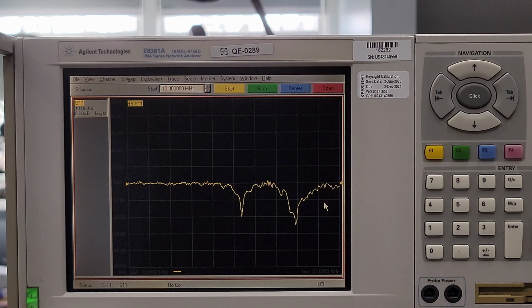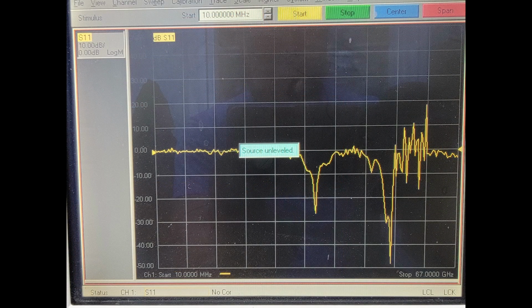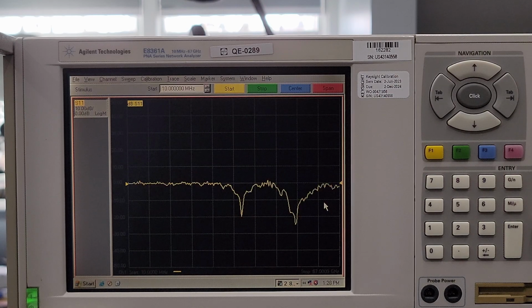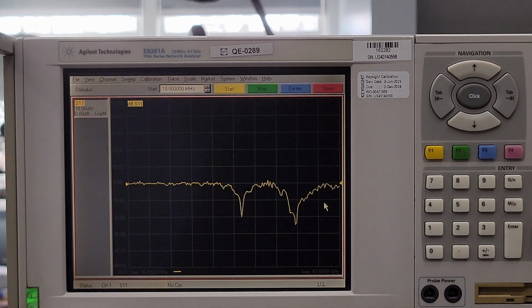The VNA appears to be sweeping normally now. There are no phase lock or source unleveled errors present. However, after sitting for a while, the phase lock source unleveled error pair will intermittently appear and disappear. Because the unit sweeps normally most of the time, and because of the intermittent EEPROM and source unleveled phase lock errors, I don't believe the issue is with a major RF assembly. My suspicion is an intermittent digital connection somewhere between a daughter board and the CPU.